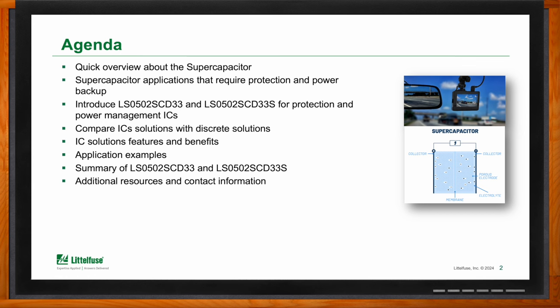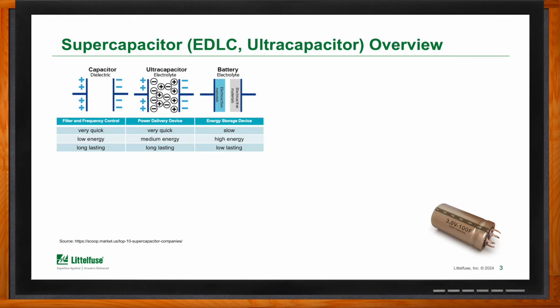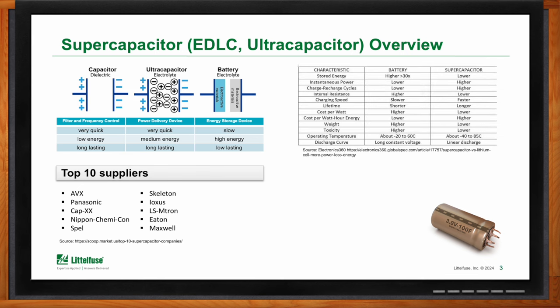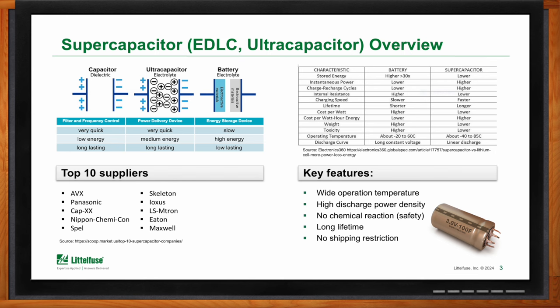Give us a brief rundown on supercapacitors. A supercapacitor falls in between a regular capacitor and a battery. A capacitor basically functions on a physical process; a battery is more of an electrochemical process. Supercapacitors are sometimes otherwise known as EDLCs, ultracapacitors, or electric double-layer capacitors. Key features and benefits include very wide operating temperatures, high discharge power densities, no chemical reactions from a safety perspective, very long lifetime, almost unlimited charge and discharge cycles, and no shipping restrictions. No chemical reaction is really the key feature, along with very high discharge rates in the end application.